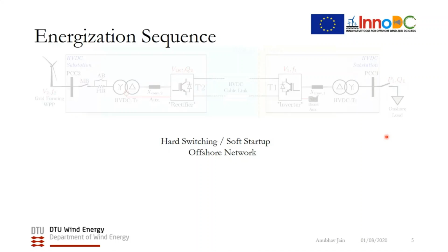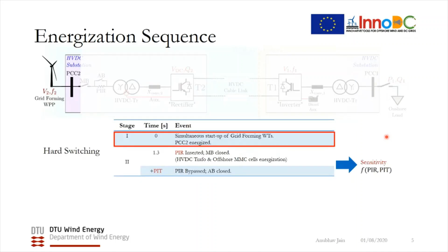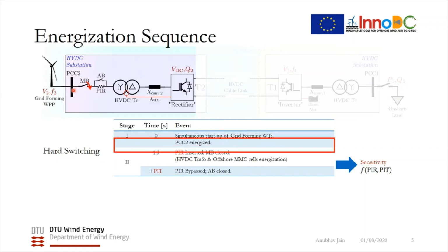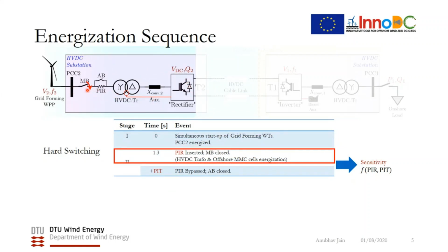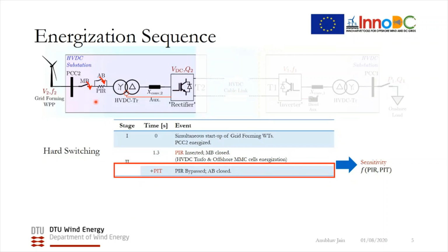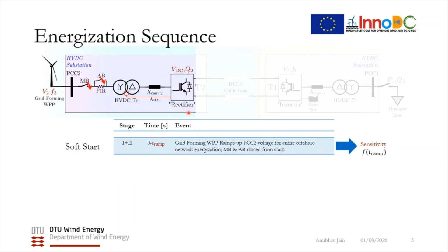So just to show the different steps of the energization sequence to give a more clearer understanding. First, we start with the offshore networks, which can be energized, as I talked before, through hard switching or using soft startup. So in the hard switching case, we energize the grid forming wind turbines. Then we connect the offshore transformer and the MMC cells through this PIR, which is then bypassed after a pre-insertion time once the transients have died down. For the soft start case, this entire network is connected from the beginning and without the PIR, and the voltage of the grid forming wind turbines is ramped up slowly to energize to keep the transients controlled.